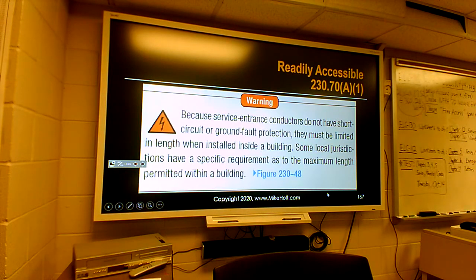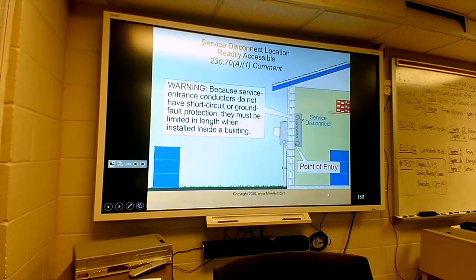They must be limited in length if they're inside the building because you don't have protection for it, because it's coming straight from the power line. And so here, they've got the meter base outside and they're running through the wall. That's like it's done at my house, it's running straight to the wall. And actually now my service disconnect is outside and inside is like a sub panel. It's considered to be a sub panel.